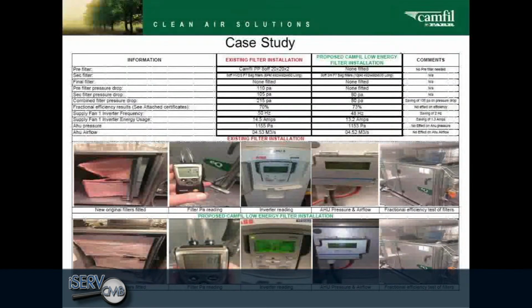But on this one, we did actually set up with a test air handling unit, and we monitored the pressure drop, the volume flow rate, and the energy consumption via the variable speed drive, and we actually changed the filters from some middle-of-the-range filters. They weren't the cheapest on the market, and we replaced them with our optimised low-energy air filters. And the reduction in pressure drop is written up there somewhere, and I can't read it now. It's about 85 pascals, I think, was the final pressure drop, and I think the initial was 215 or something like that.